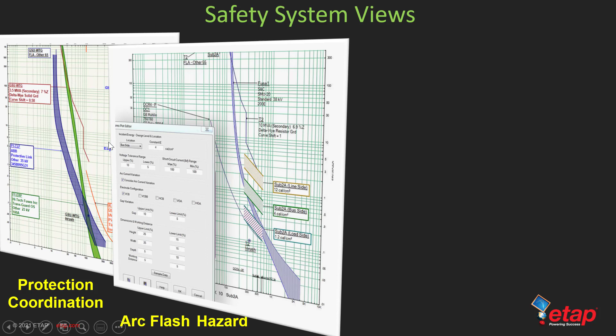It works directly with a one-line diagram. You can create one and move them around graphically. Then you have the same thing for the arc flash hazard time current characteristics. Then you have the distance relays or impedance relays that here are shown the X over R graphs. Then you have the ground grid, which is really IEEE and IEC standards, and also finite element method, which would work for any configuration you like to have.